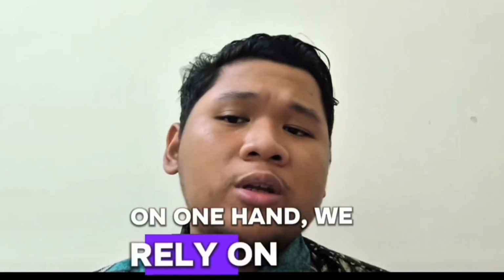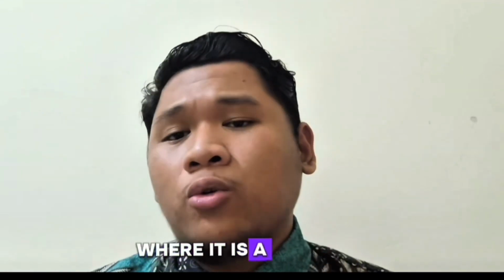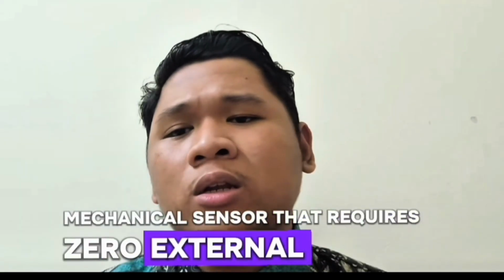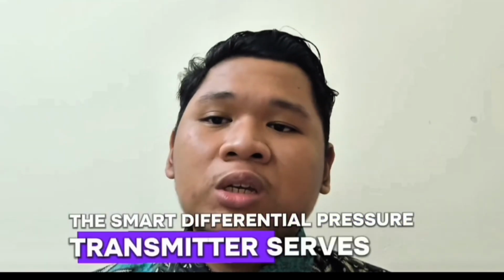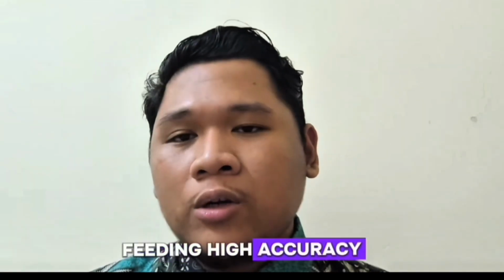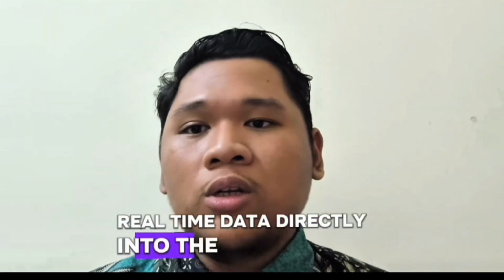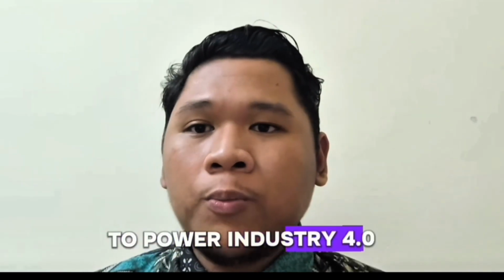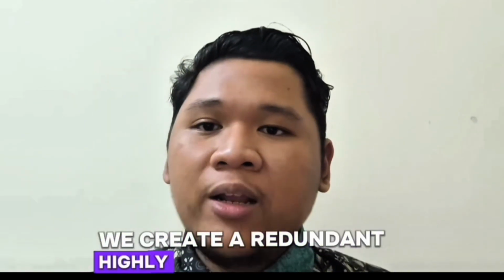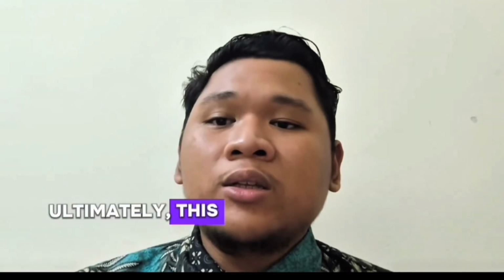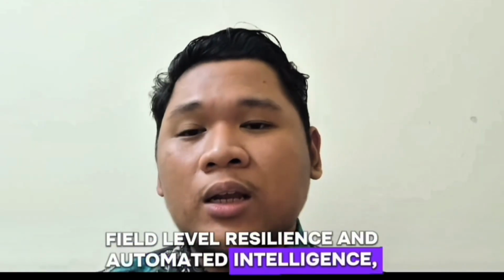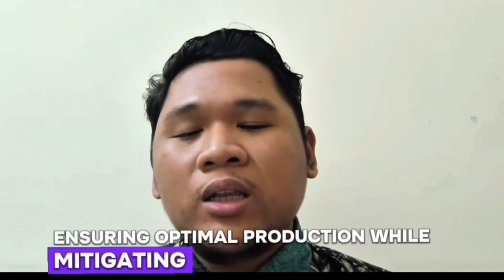On one hand, we rely on the traditional Bourdon tube pressure gauge, a robust mechanical sentinel that requires zero external power for local field verification. On the other hand, the smart differential pressure transmitter serves as our digital nervous system, feeding high accuracy, real-time data directly into the distributed control system to power Industry 4.0 automation. By aligning these technologies under rigorous API and ASME standards, we create a redundant, highly reliable ecosystem. Ultimately, this integration bridges the gap between field-level resilience and automated intelligence, ensuring optimal production while mitigating operational risks.